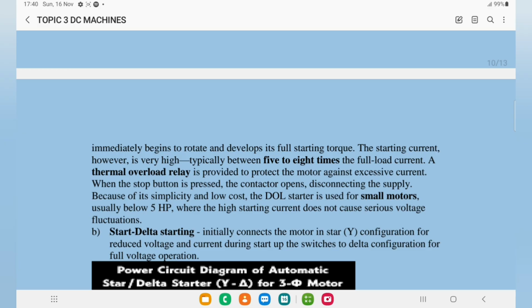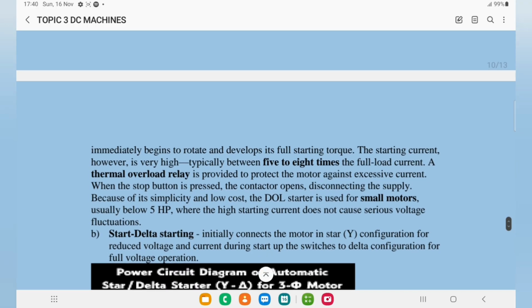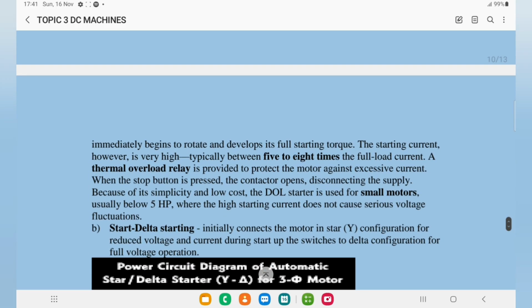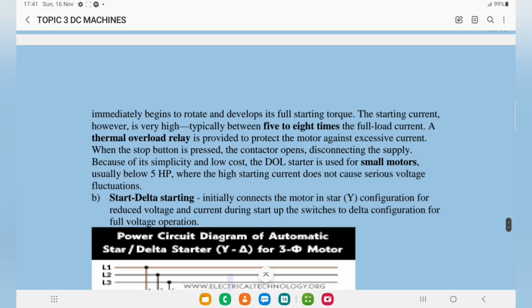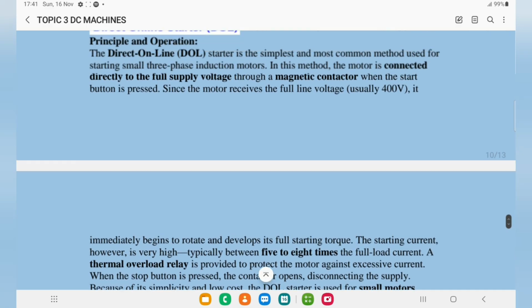However, there is a high starting current that is usually 5 to 8 times the full load current, and that's why a thermal overload relay is provided in order to protect the motor from excessive current. When the stop button is pressed, the contactor will open, thus disconnecting the supply. Because of its simplicity and low cost, the direct online starter is used for small motors, usually below 5 horsepower, where the high starting current does not cause serious voltage fluctuations.